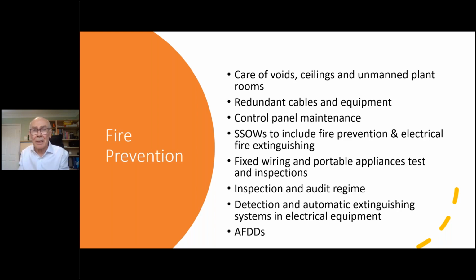AFDDs, arc fault detection devices, are there purely to pick up the low-level arcing that may occur, such as series arcing where you've got broken wires, or arcing in equipment at low voltage, and they disconnect those circuits before they become worse and turn into fires.